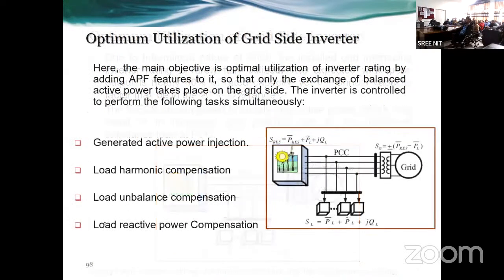So what I suggested is that if I can control the inverter in such a way that it can supply the generated power, PRES, which it was generating in the previous case, plus this part also from the inverter, then on the grid side I have only the exchange of balanced active power, meaning the deficit amount. If I am generating less from renewable and then consuming, then I have to take some power from the grid. Or if I am generating more, then I have to give power to the grid.